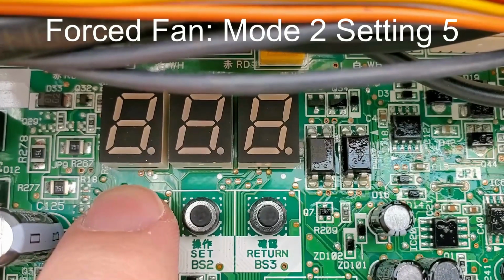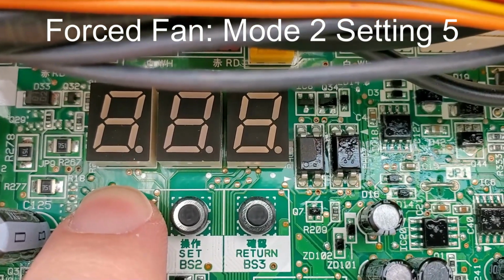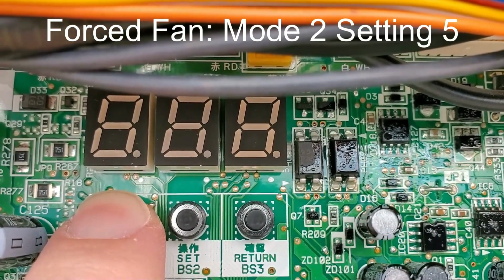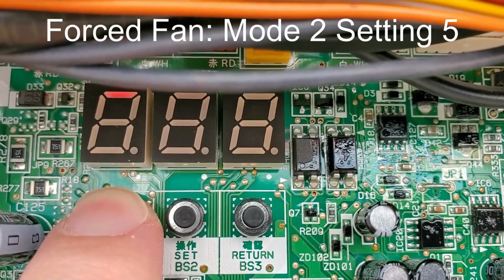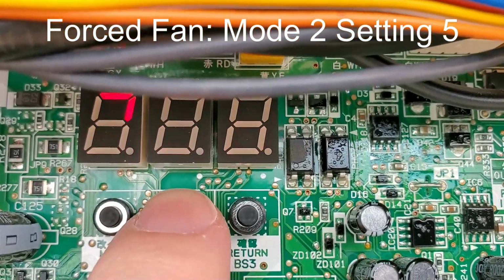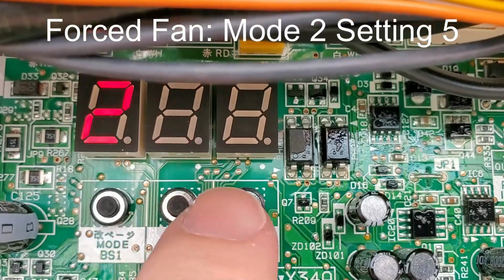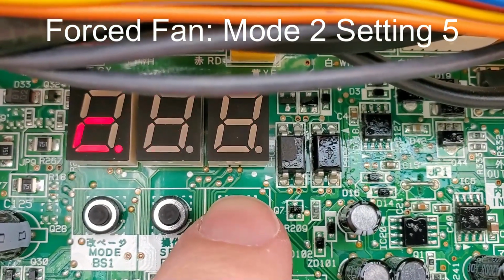now you are going to be adding an indoor unit or multiple indoor units onto the communication network. So you need to tell the outdoor unit to readdress during the initialization process. On newer boards, so VRV4 generation and later, again, start from the blank screen, and the button sequence is actually the same. Press and hold the mode button until 2.00 is flashing. 2.00 is service mode 2, and then you're going to press set 5 times, so you should have 2.05. Then press return 1 time.